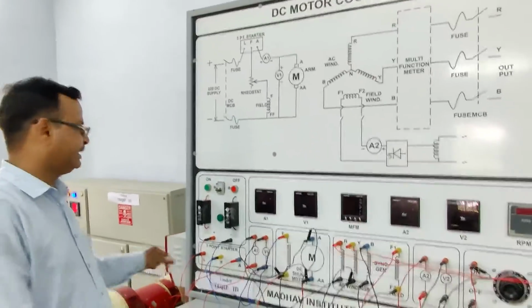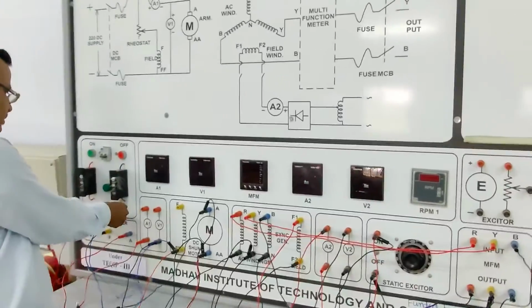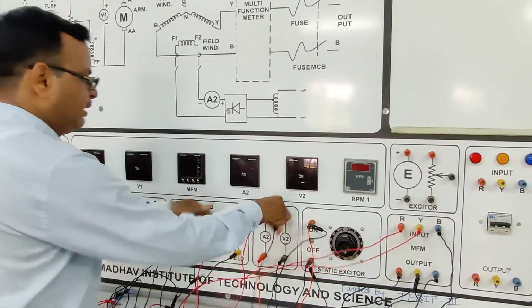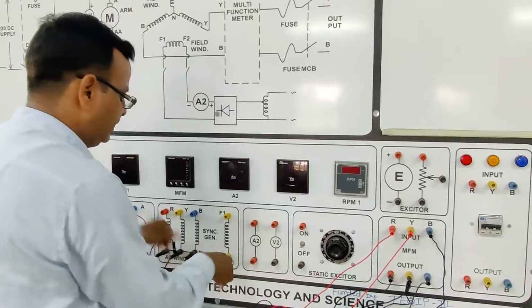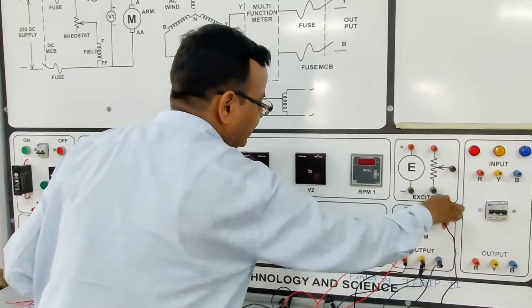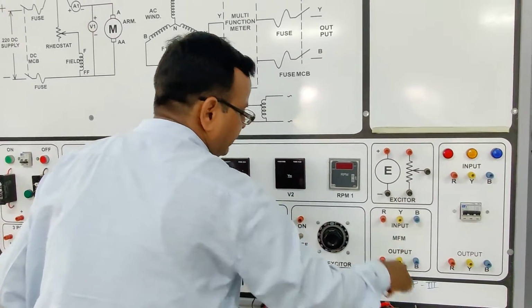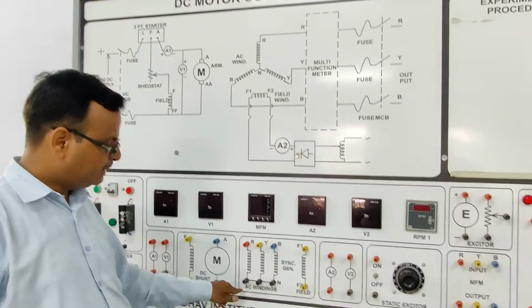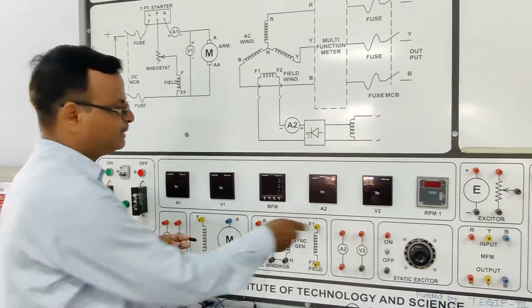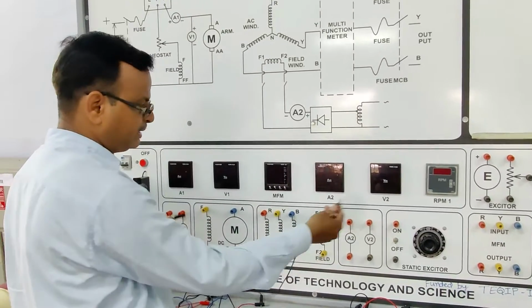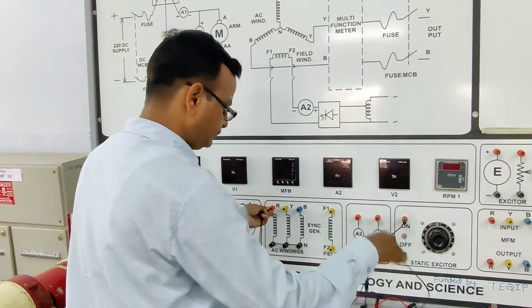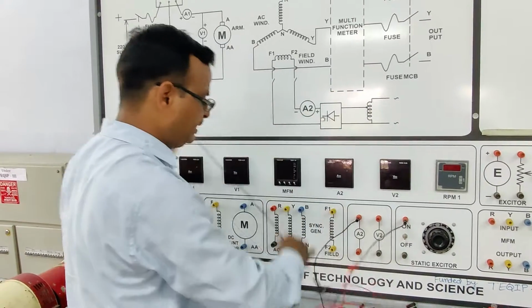The stator winding resistance means remove all the terminals and we will calculate the stator winding resistance. How to calculate the stator winding resistance? Simply we can calculate using Ohm's law. These are stator winding terminals, these are internally connected, so we keep the DC supply across any 2 phase like this.